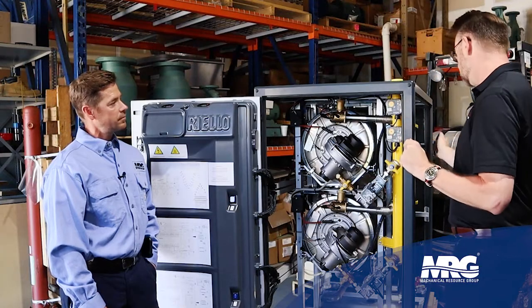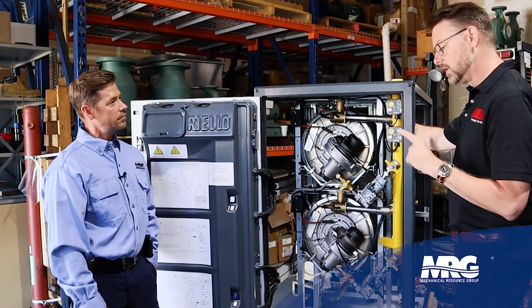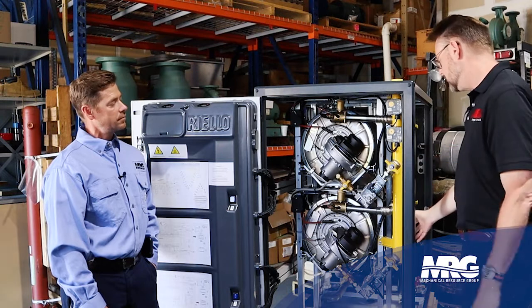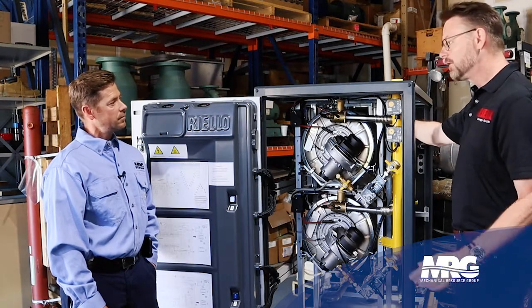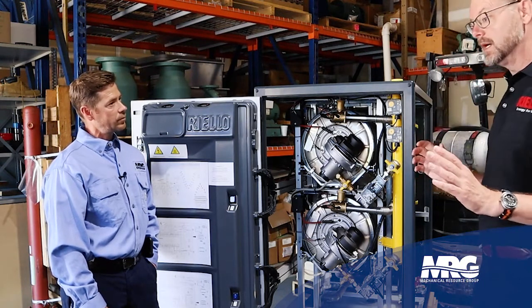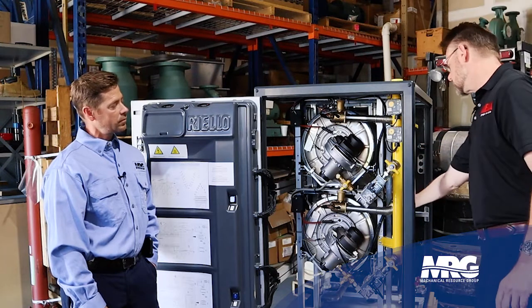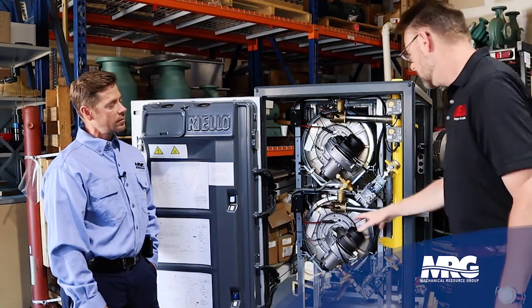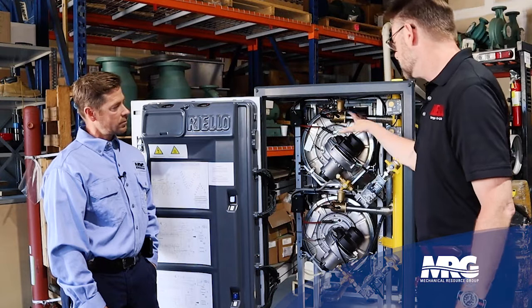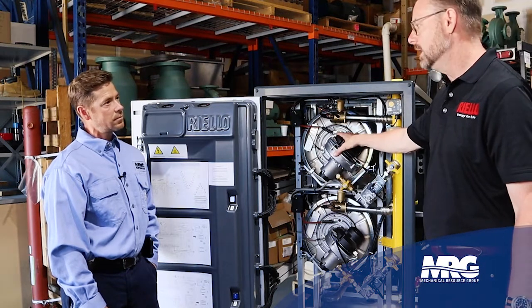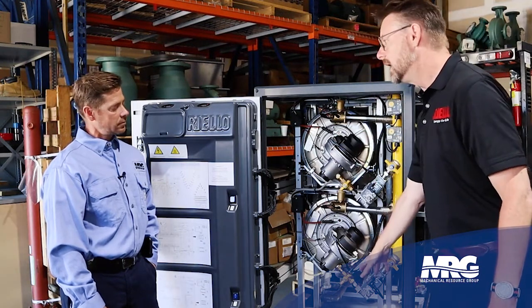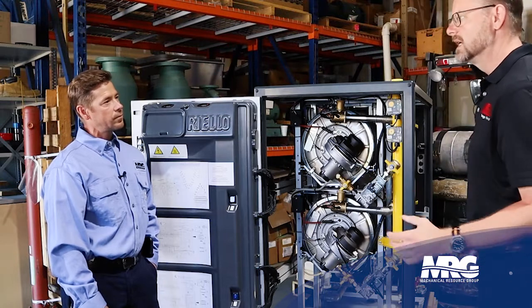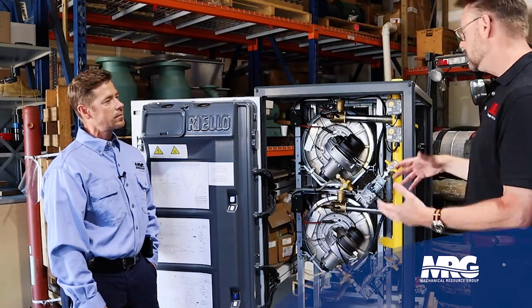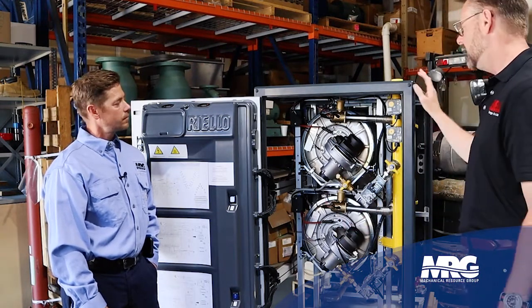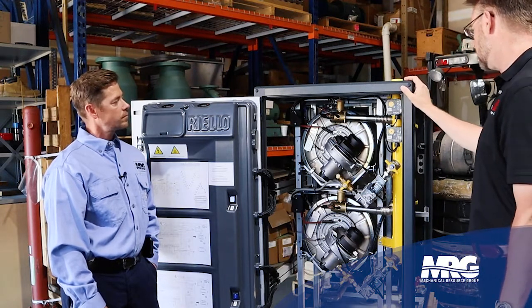In the case here, because the flow measurement, the flow proving, exists on each of the heat engines, that failure of our flow meter here, let's not pick on Helix number 1. Let's say Helix number 2 had a failed flow meter. Helix number 2 goes down. Helix number 1 continues to operate. Helix number 3 would continue to operate. 4, 5, 6, 7, 8 would continue to operate. We would only be down that specific heat engine capacity. Okay, so that was a flow-related issue.